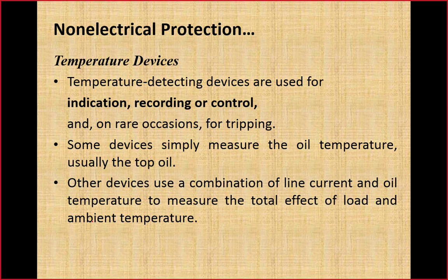Other devices use a combination of the oil temperature as well as the current that the transformer is carrying to have the complete detail of the reason why the temperature is rising, whether it is due to the ambient condition or due to the increase in load. It is quite possible that if the cooling mechanism of the transformer is not working, temperature may rise but current is not greater than the rated value. So that is a clear indication that something has happened to the cooling mechanism of the transformer.